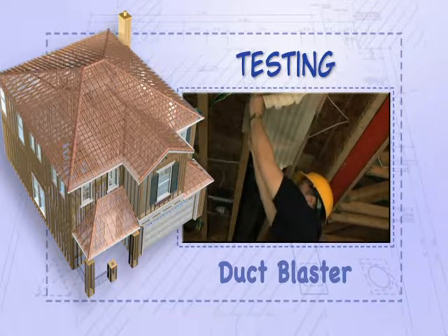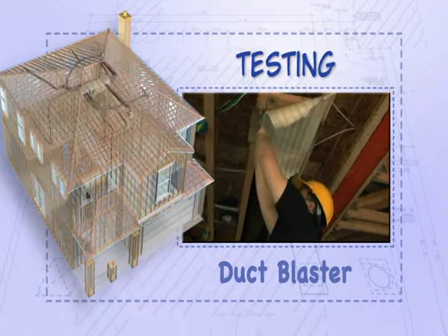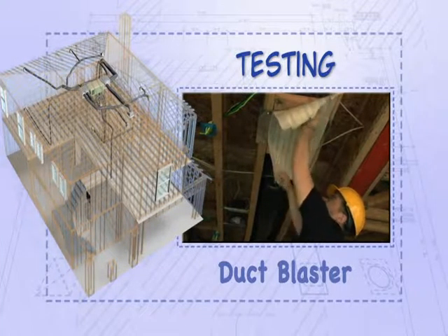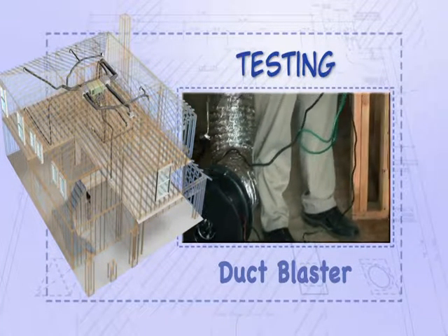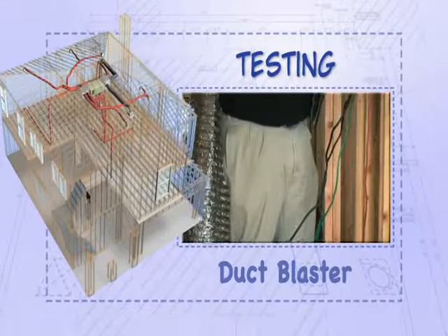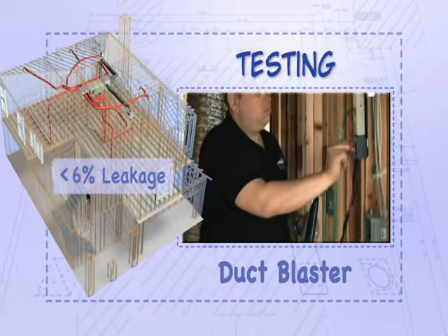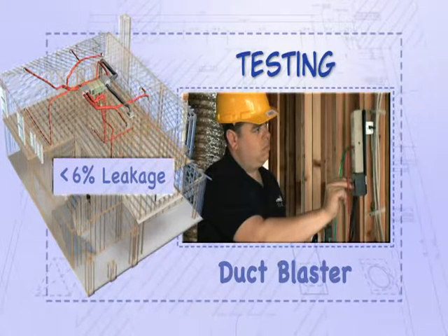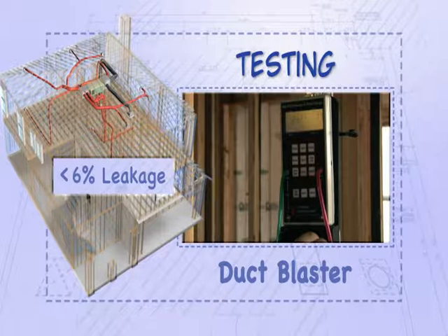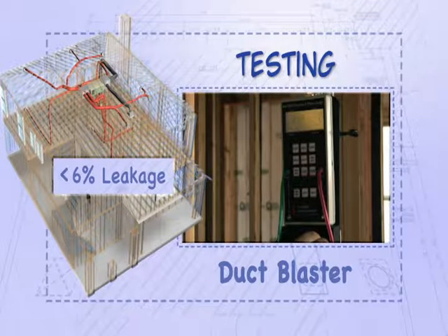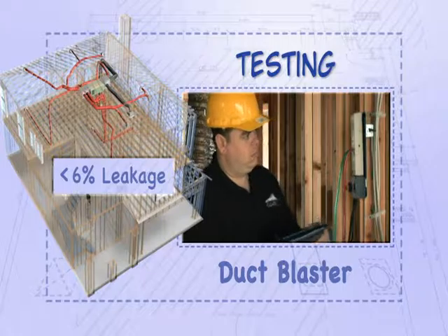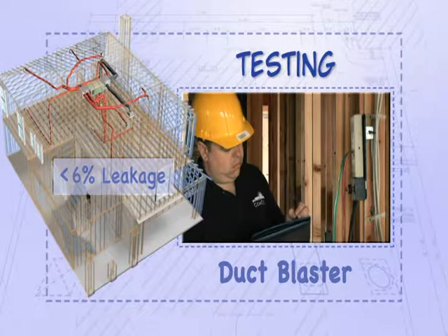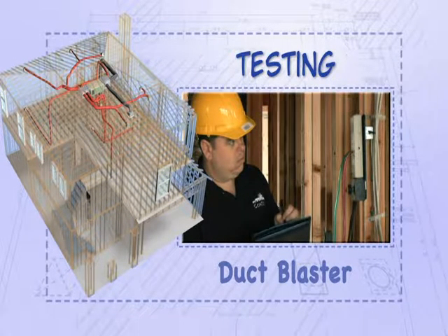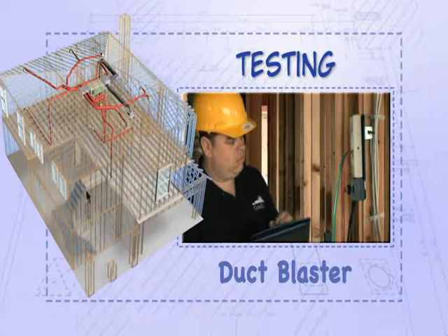The duct blaster test measures for leaks in all the ducts. What happens is the registers are sealed and a blower pressurizes the entire system. Then a gauge measures how much air is escaping, which must be less than 6%. If ducts leak, and ducts in typical older homes leak as much as 20% or more, it's like money leaking out. As if every time you turned on the hot water, a quarter of it leaked from the pipes under the house. A big waste.